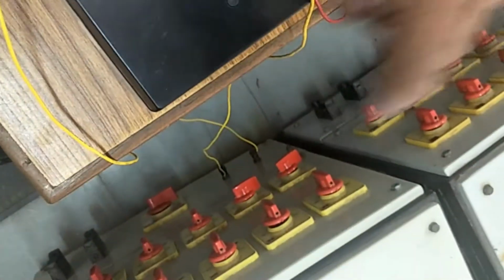That means the two loads should be turned on in such a way that the secondary side of the teaser ammeter and the main transformer ammeter should read the same. Then only we say that it is balanced load. Is it clear? So like this, for balanced load conditions you have to note down.